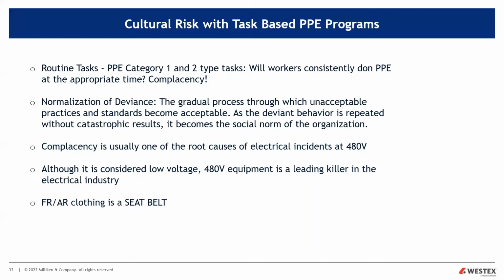Okay, so if you got your flame-resistant arc-rated clothing on, just like a seatbelt, they're both constant, proximate, tactile triggers to set your appropriate safety mindset so that you can access your safety training. So your clothing, even more than a seatbelt, because you tend to forget about the seatbelt over time, it's a constant, proximate, tactile, you can feel it. And when you extend your arms out, you can see that I'm wearing flame-resistant arc-rated sleeves. Oh, it's a trigger to access the mindset to, oh, I should probably put voltage-rated gloves over my flame-resistant arc-rated sleeves. Oh, I should put my task-based headgear. So think about it. A daily wear can be a protective measure and a preventative measure because it's there.